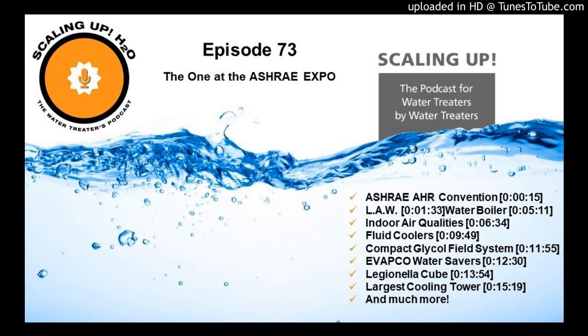So it's a really impressive unit. It's very compact. So this isn't a trade show model, this is it. Yes, this is a full-scale 12-cylinder Evapco water saver. So we'd be looking at about 25 to 30 GPM of average makeup that this could give to your evaporative unit. It comes in 9 different sizes, so we can go as small as a 3-cylinder setup as well as up to 24 cylinders. So we kind of size them based on the makeup water quality as well as your load, is your size of your system.